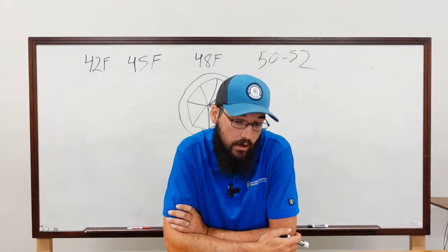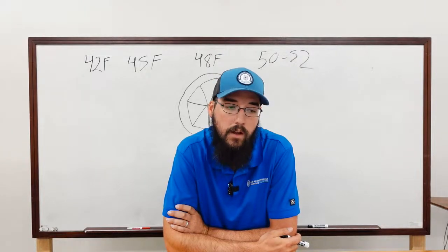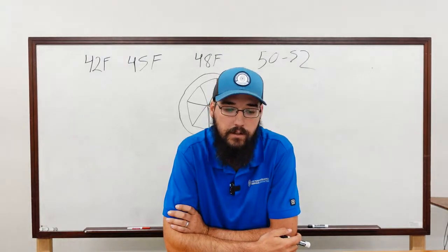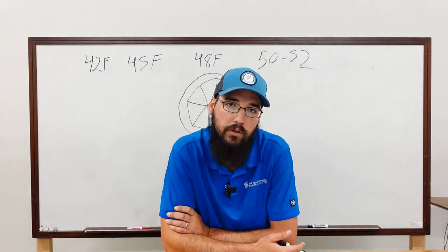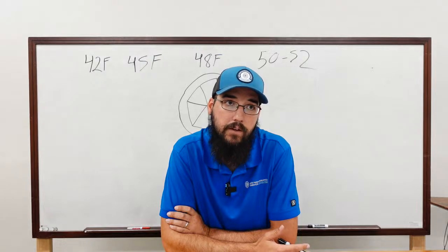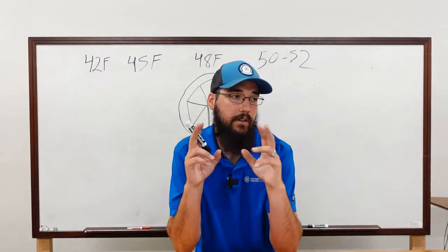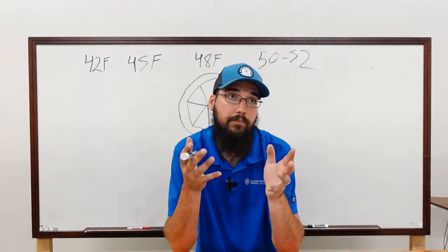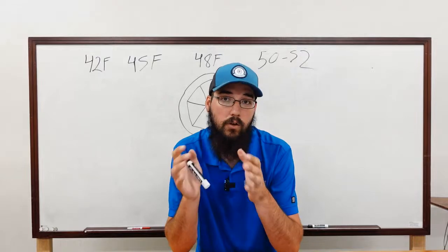Anyway, ultimately, no. They don't like low loads for long periods of time, but they will do it, just like a screw will. Depending on the exact conditions, yes, it could lead to oil return issues, migration issues. It could lead to things. But something we have more control of with water-cooled equipment is our condenser side. So even if we're in a low load condition, we can manipulate our condenser water set point to give the compressor more lift and load, or whatever parameters you need in order to maintain oil return and things. That is a lot harder to do, if even possible, with an air-cooled machine. We can take that a whole lot further with a water-cooled.